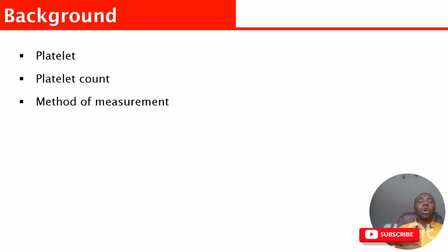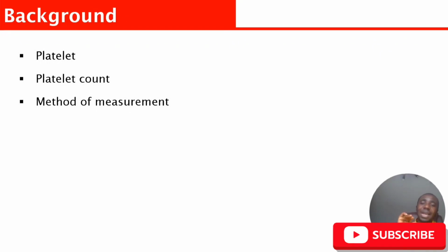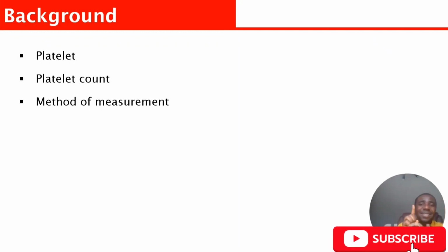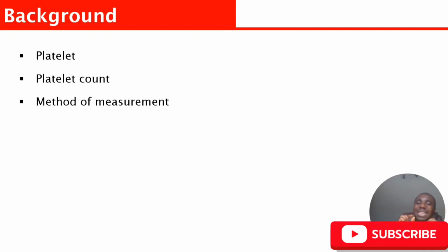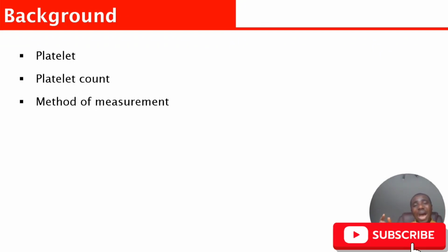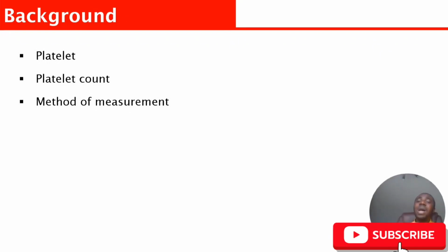Remember, it is not only platelets. Through the apertures, white cells can pass, red blood cells can pass, and of course platelets will also pass. Anyway, as the platelet is passing, based on the normal size of the platelet, that is how the analyzer can measure the amount of platelet in that very sample. So as the platelet continues to pass, it will continue to count it.